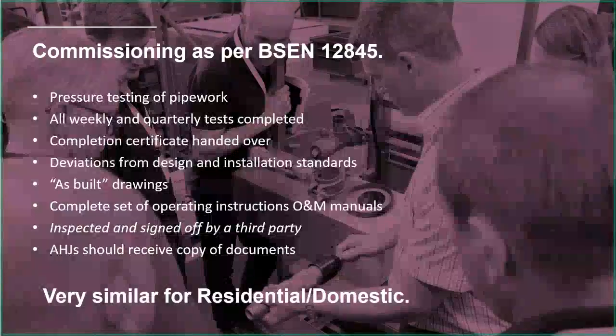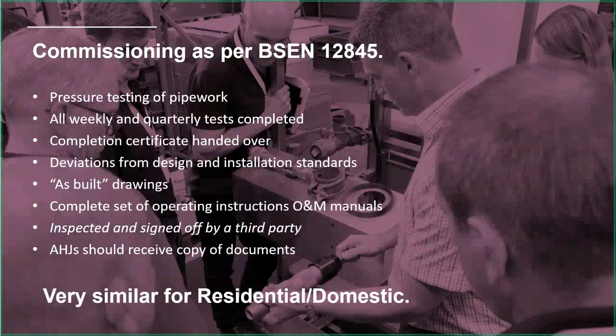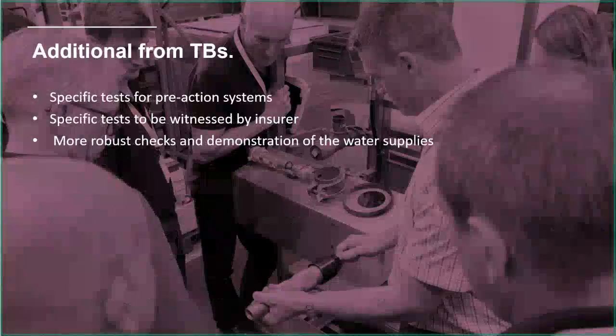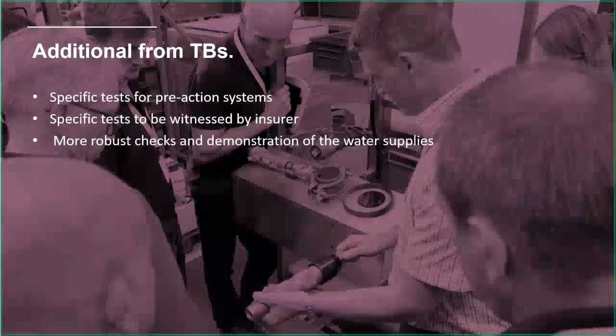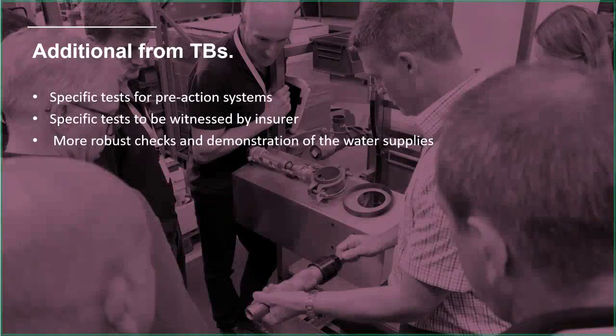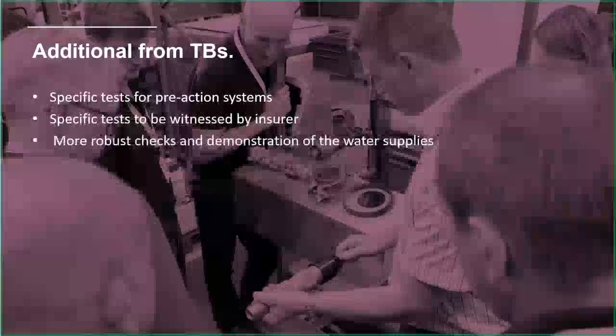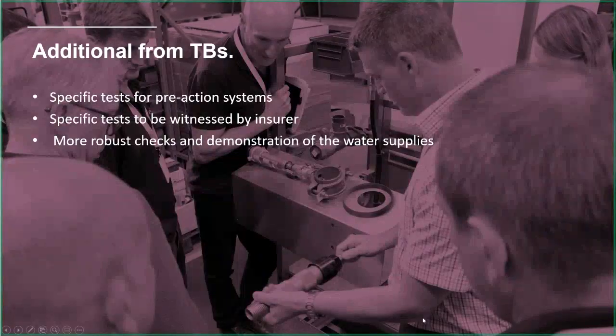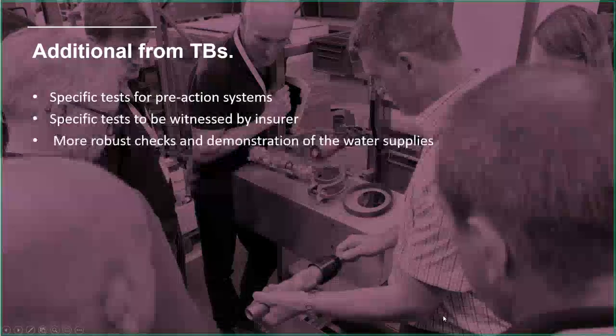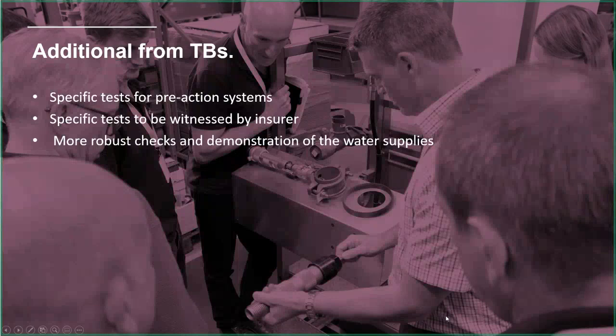Very similar for residential and domestic in terms of what needs to happen, but obviously it's on a slightly smaller scale generally, residential and domestic rather than industrial or commercial. There's some additional information from the technical bulletins. For example, pre-action systems aren't really mentioned in 12845, so there are specific tests for pre-action systems. There's a section that's all to do with the insurer, depending on whether it's property protection or life safety. If it's property protection, the insurer is going to be involved a great deal more, so there are special instructions for that. And there are some more robust checks and demonstrations of the water supplies. 12845 is a bit looser in terms of what exactly needs to be demonstrated, which is more clearly defined in the technical bulletins.